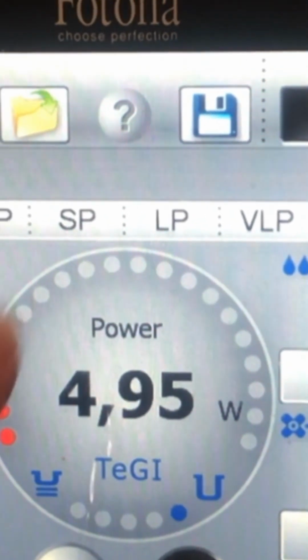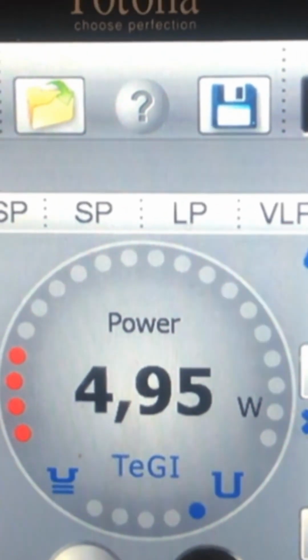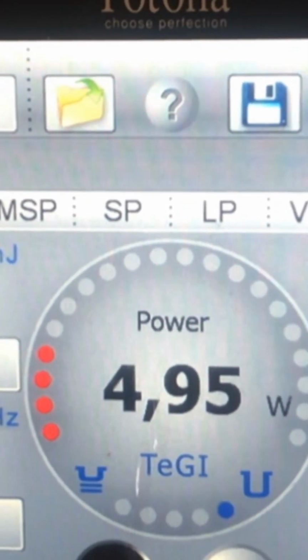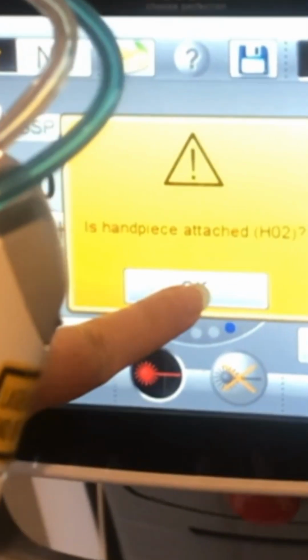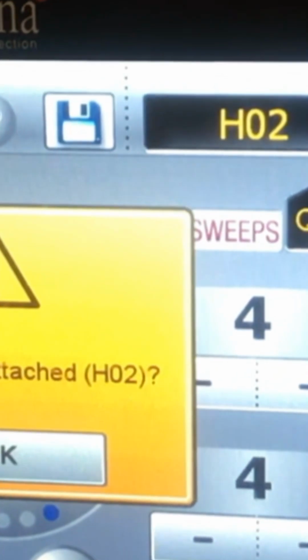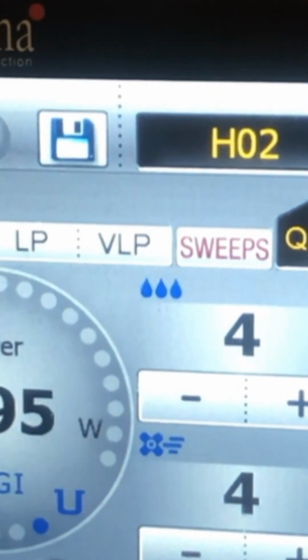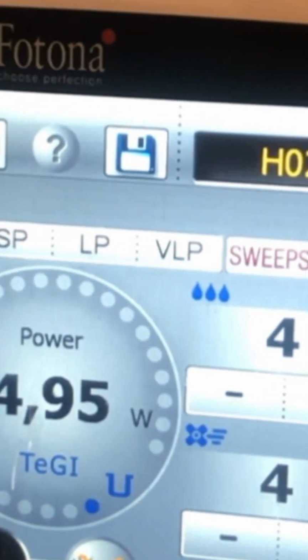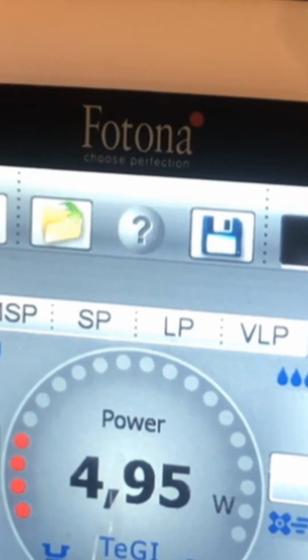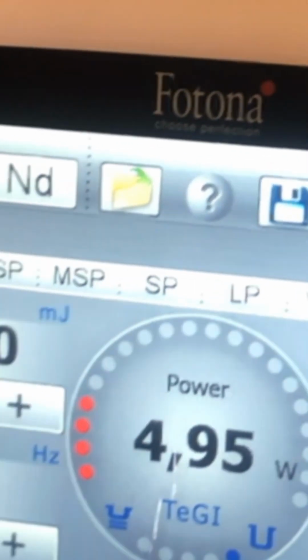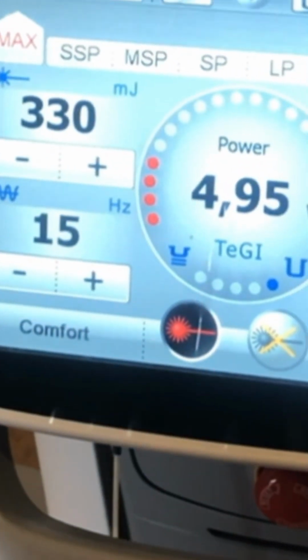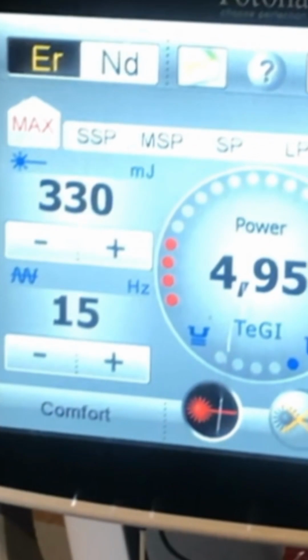If we want to activate the laser, this button here activates the laser, which once the laser is on, it's going to ask you, do you have the correct handpiece? It's always going to ask you that as a precaution. The next thing you're going to see is this goes red. That's a sign that the laser is working. And the next thing you want to look for is the aiming beam. Okay, so always when you turn the laser on, first check for red, then check the aiming beam, and then you can begin going to the patient for care.